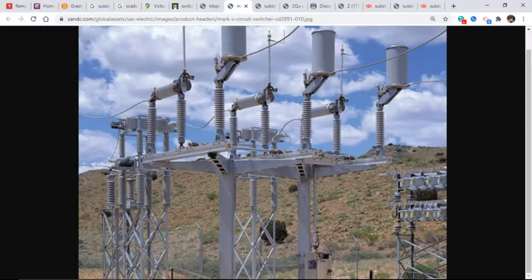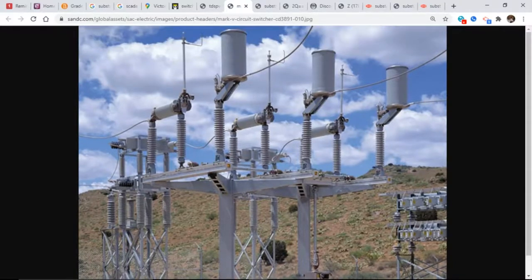It is also linked by SCADA, which we talked about before. And it's also linked within the substation. So if there is a fault on the transformer or beyond up to the breaker, a signal is going to be sent to this, and this will automatically open up the circuit. Remember, our transformer in the substation is the most expensive piece of equipment I have in my electrical system outside of the generating station. So in distribution, that transformer needs to have a lot of protection on it, and it needs to be real fast.